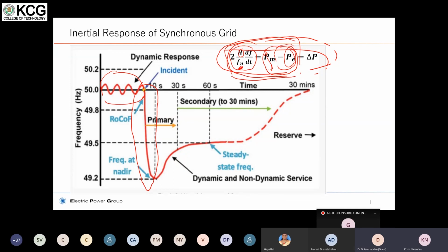When you lose generation, you have to support the load with extra power, whatever is required. This extra power is derived from devices which still have the capability to generate. For example, if an inverter system is designed for 300 megawatt and you are operating only at 200 megawatt, then you still have 100 megawatt available to support the virtual inertia in the system. So that's how it is done.